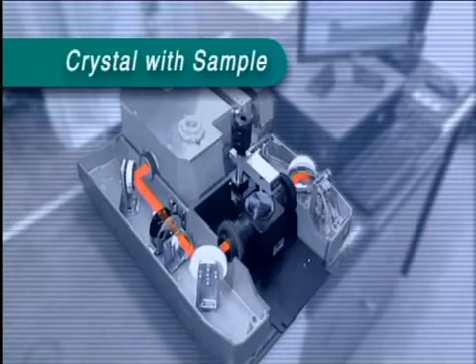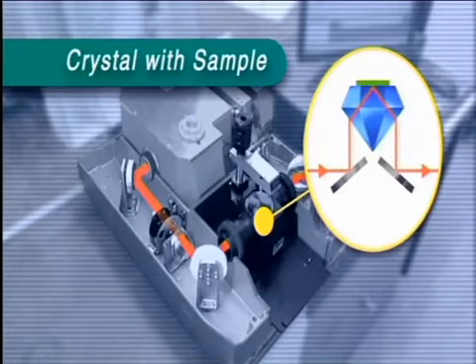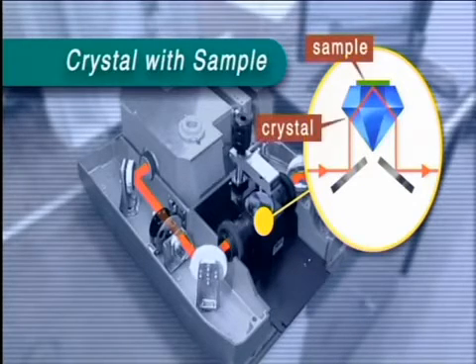This is the sample holder. The sample is placed here on a crystal which is made of diamond or germanium. The IR beam is directed into the sample by a mirror. It is reflected back from the upper surface of the sample before being guided into the detector by a second mirror. This method is called attenuated total reflection or ATR.